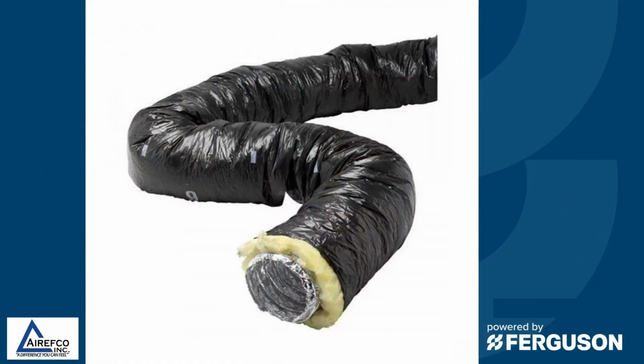Flex duct comes compressed in boxes, and when it is taken out of the box, the proper design for a flex duct is to have it stretched out completely so that the airflow through the flex duct does not bounce around and bounce off the walls as it makes its way around curves and over rafters. So the flex duct needs to be stretched out completely and properly supported.